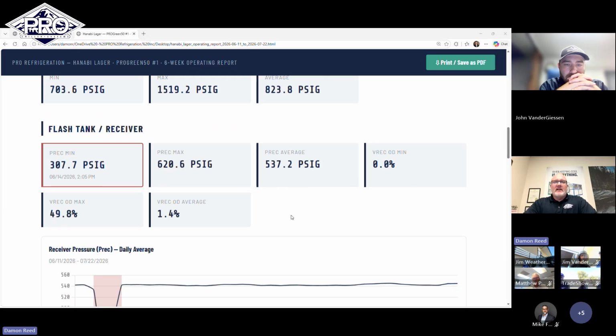The flash tank and receiver, and forgive me for some of the vernacular here, which is driven by the tags used in the control software. But basically, this red box highlighting our minimum receiver says our receiver pressure got down to 307 psi. We have a set point in the control system for what's called a flash gas bypass valve. It's basically an automated valve that regulates your receiver pressure, and that's set to maintain 500 psi. 551, I think, is the exact number.